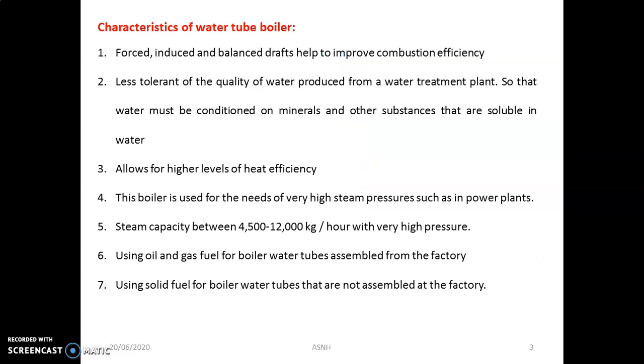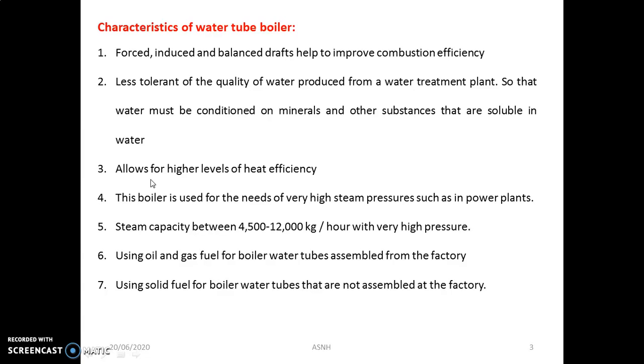Here are some important characteristics of the water tube boiler. Forced, induced, and balanced draft help to improve combustion efficiency. It is less tolerant of water quality from the treatment plant, so water must be conditioned and pH level must be maintained. It allows a higher level of heat efficiency — the efficiency of the water tube boiler is around 90%, whereas for the fire tube boiler it is between 60 to 75%.